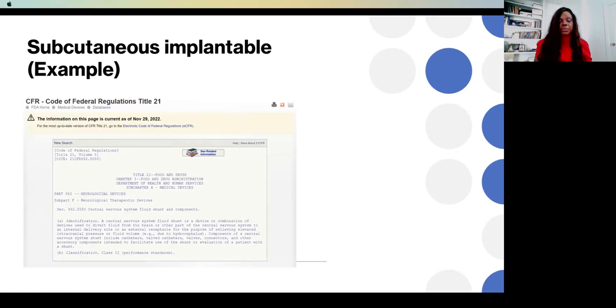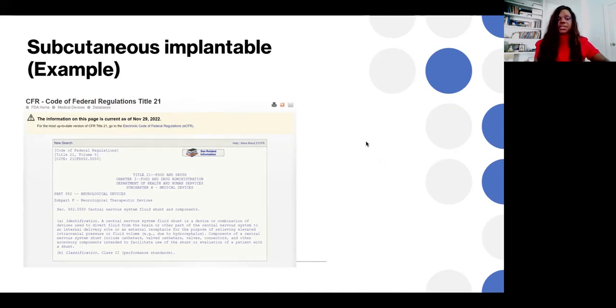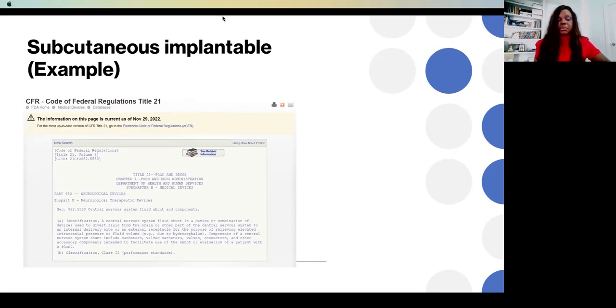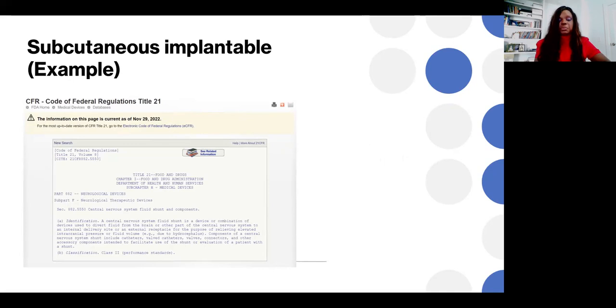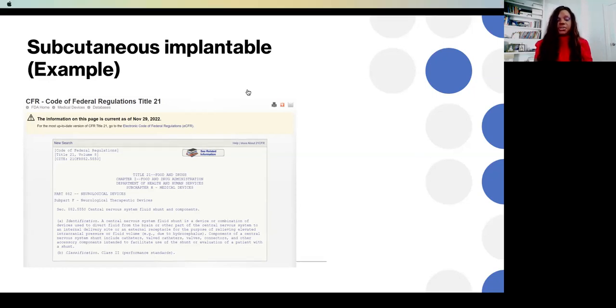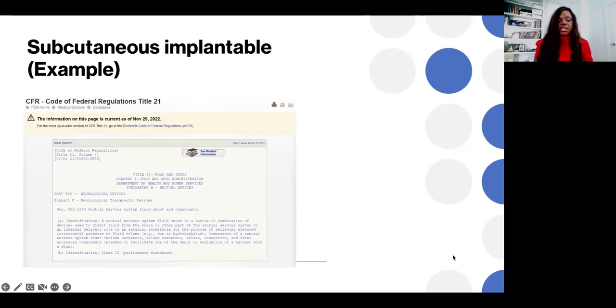So this describes exactly what the intended use is for these devices that are on the market. If there's additional information based on the test that you are developing that is not here, then that's when you really would need to go to the FDA and ask a question, because your device might be a little different from the intended use that is here. And as you can see, the classification is also telling you that there are performance standards that are applicable. So these are the regulatory controls. Next slide, please.